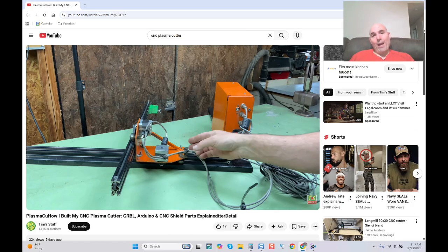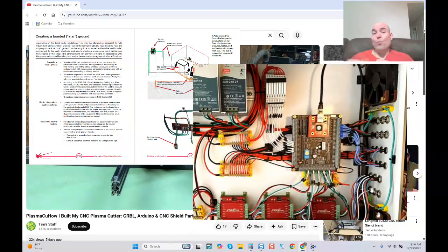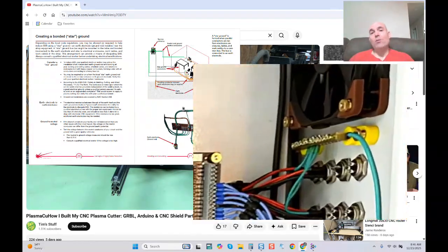And on top of that, when you have interference, the natural instinct most guys do, and I hear this all the time, is, and just as we see here, they'll install ferrite, then they start shielding everything. But the problem is they don't understand what tools they're using. You install a ferrite, where do you install a ferrite? What is the frequency you're using on the ferrite? When you're using shielded cable, are you installing the correct shielded cable, single shielded Mylar foil, or is it double shielded, which is required for robotics? Is it properly ground drained? Do we have a ground inside of our electronics enclosure, which is required?